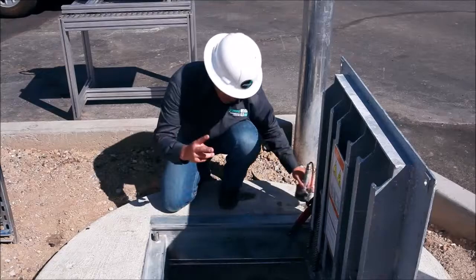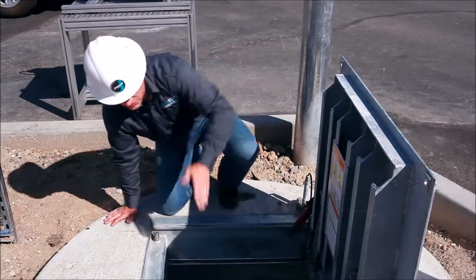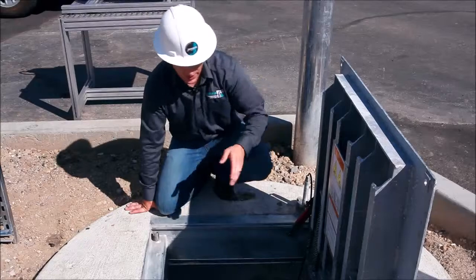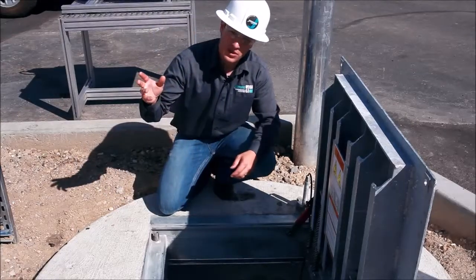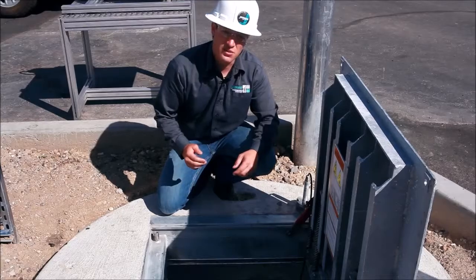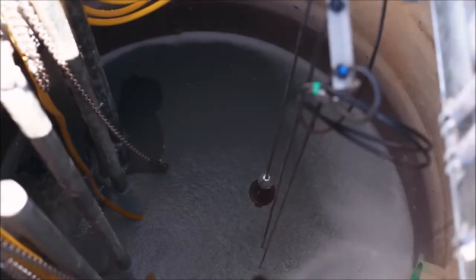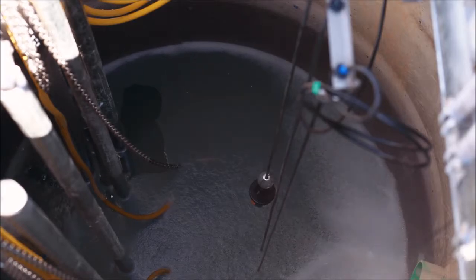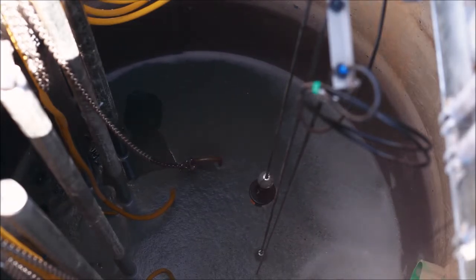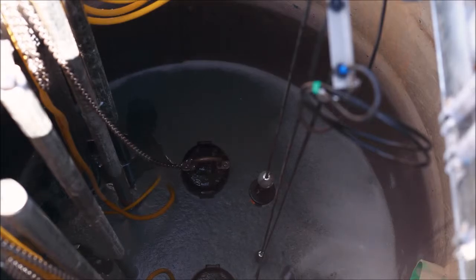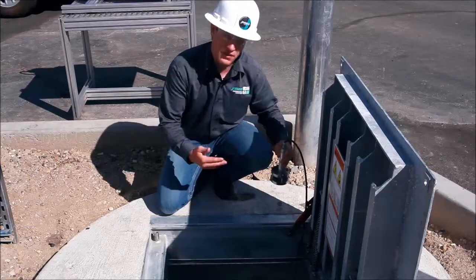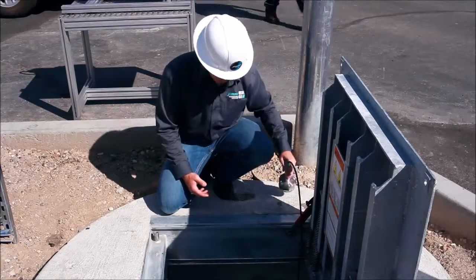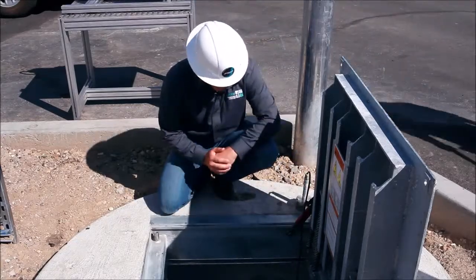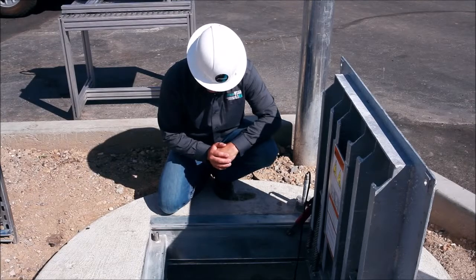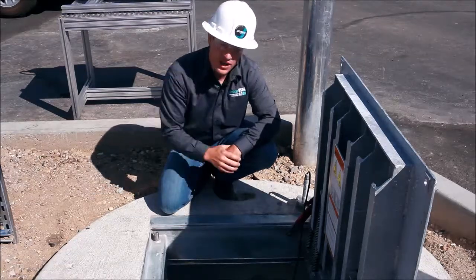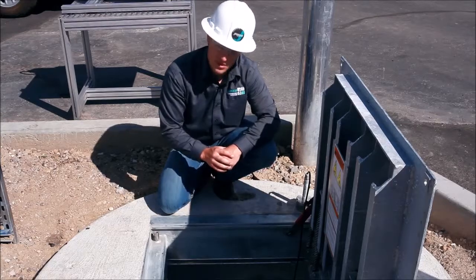We have two backup floats in the wet well. Those are manufactured by Reno Controls. We'll talk a little bit more about the Reno Controls control panel, but we utilize the floats as basically a backup, redundant feature. So we have a low water float and a high water float. Both of those floats serve in the event that the pressure transducer was to fail, so that the station doesn't go unoperational. But those devices during normal pump cycles are not being utilized. Both pumps are, like I said, on an auto guide rail system. That's basically it for the wet well. We're going to talk a little bit more about the pumps, and as you'll see behind me in a moment, we actually have a cutaway pump, and we'll go into some of the specifics on the pumps.